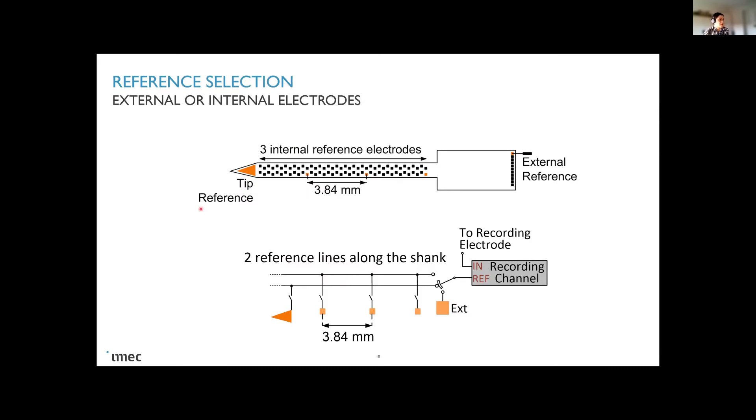For the references, we have several options in 2.0. We have a large tip electrode that can be used as a reference. We also have the possibility to connect an external electrode to a large pad. Or we have also the possibility to select some small recording pixels as references. Each channel can select which of these different options as a reference. So each channel can independently have a reference. And normally, I think for most of the use cases, a single reference is used. But there must be some experiments where having different references can be interesting.